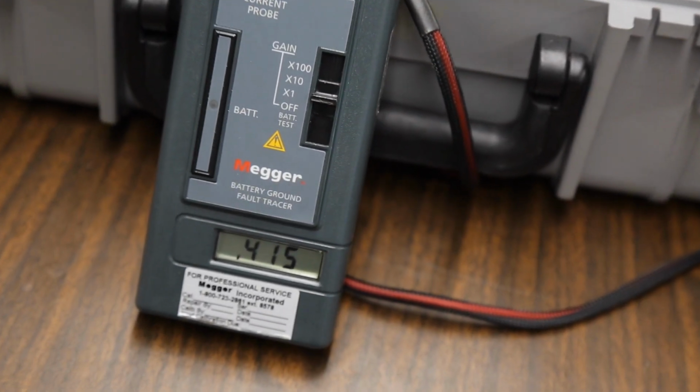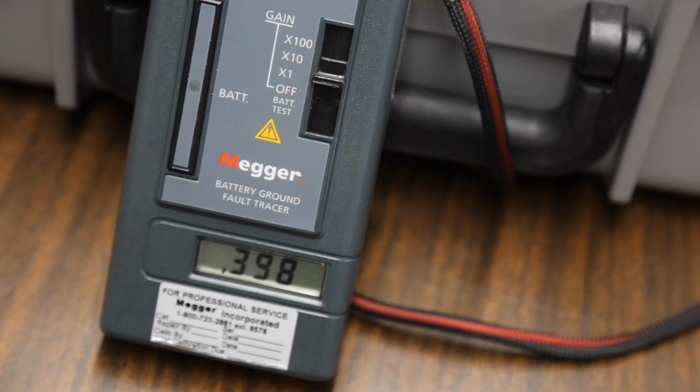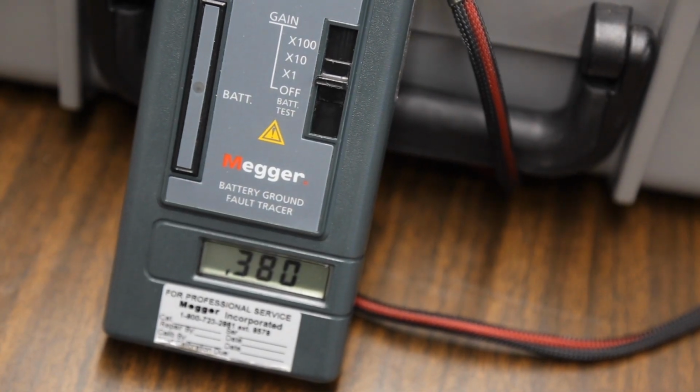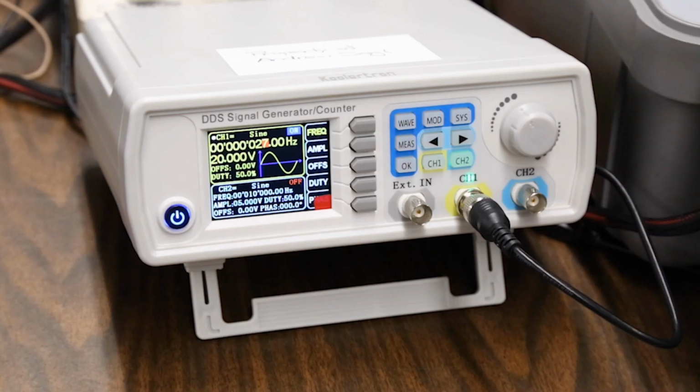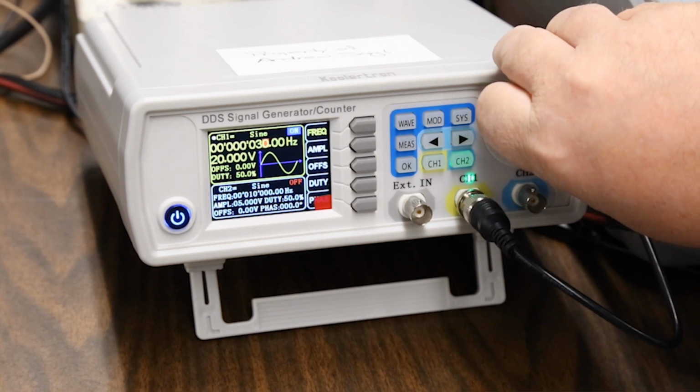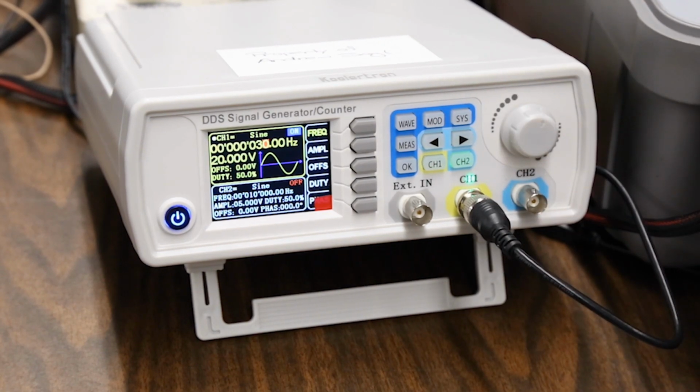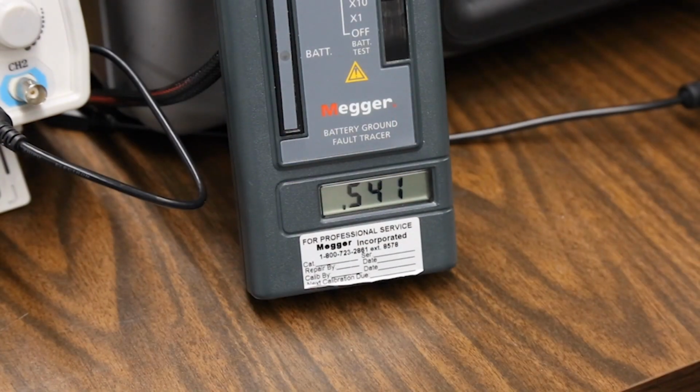The measured value will not stabilize. This can be due to low frequency oscillations on the line. As the frequency of the oscillation increases, the effect on the measured value decreases. As the frequency increases to 2 Hz and 3 Hz, the effects on the measured value are beginning to decrease.